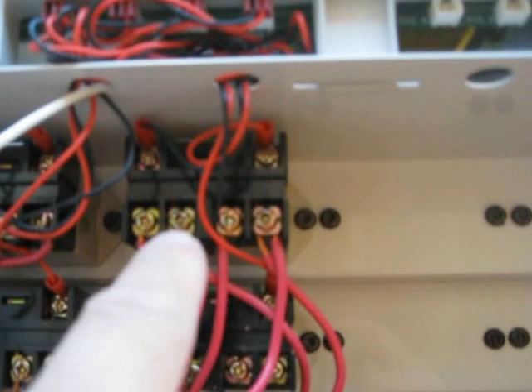I think there's 4 relays, and this relay on the top here is connected to the filter pump. I stuck a probe there, and there's no voltage at all, even with the filter pump on, and it's at service mode, and the filter pump on. There's no power there.